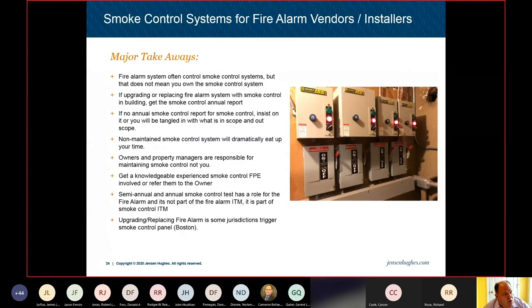So, for smoke control systems, for fire alarm vendors and installers, I wanted to give you some major takeaways. Fire alarm systems often control the smoke control systems, but that does not mean you own the smoke control system, right? It's no different than interfacing with the elevators, right? You're doing maybe a recall or an alternate floor or a hat, whatever, interfacing with that. They're separate systems, but the fire alarm system is integrated to the smoke control system to make up the smoke control system. NFPA 72 testing doesn't make you compliant with all the inspection, testing, and maintenance required for the smoke control system. It makes you compliant with the fire alarm portion of your 72 requirements.